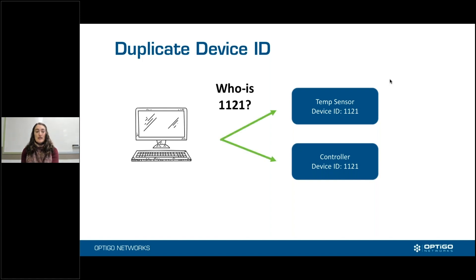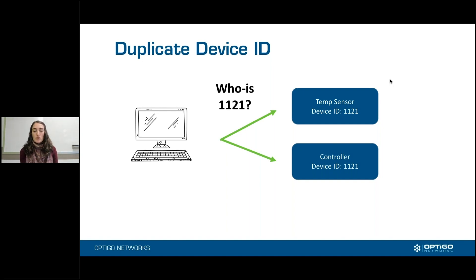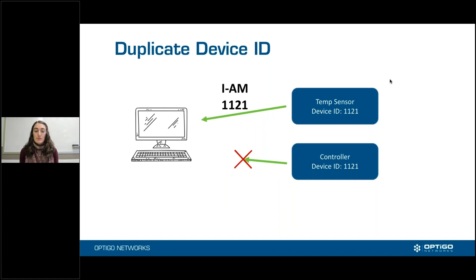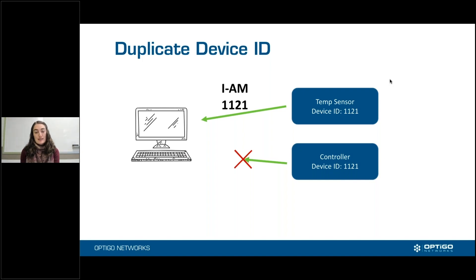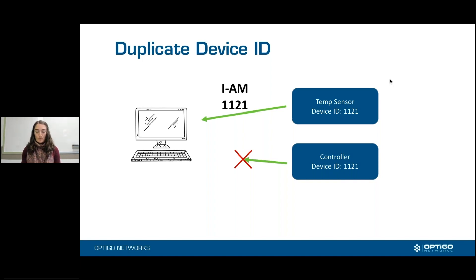Basically, what happens in this scenario is your main server will send out a message — in this example, a who-is — saying who is 1121, or maybe just a global who-is asking who all the devices are. They will probably both respond, but whichever one gets there first, the BMS is going to say: you are device 1121, and it won't listen to the other response. So the temperature sensor gets registered as 1121, and the controller is going to be pushed aside.